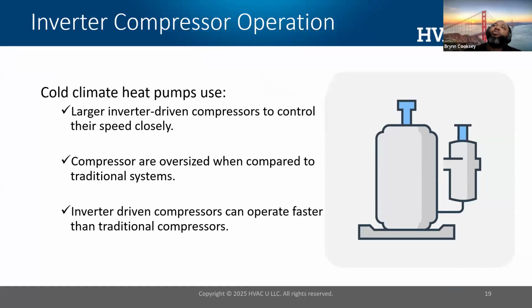One of the ways we're able to do that is through use of an inverter compressor operation. When we think about an inverter compressor, I want you to think about a device inside the heat pump that's able to precisely control the capacity of the heat pump based on the demand. Older heat pumps were fixed speed, where they would turn on and turn off. Newer heat pumps, because we have the ability to control the compressor speed, can modulate the output and in some cases even make the compressors run faster to deliver more output if needed. That's technology that we did not have in the past. So these cold climate heat pumps are able to do what they do through the use of a compressor.